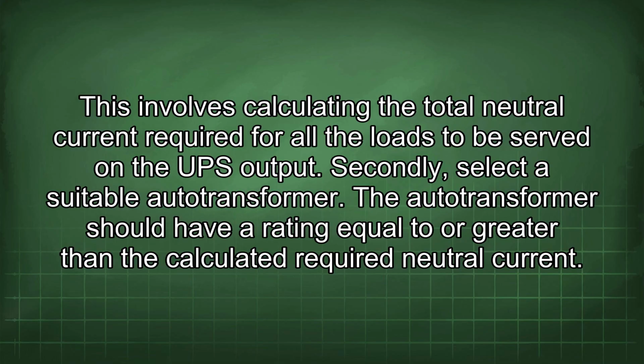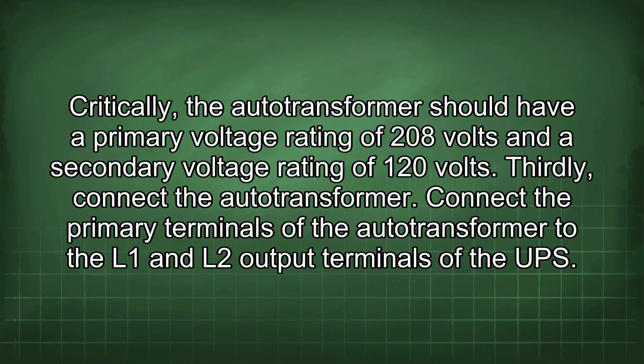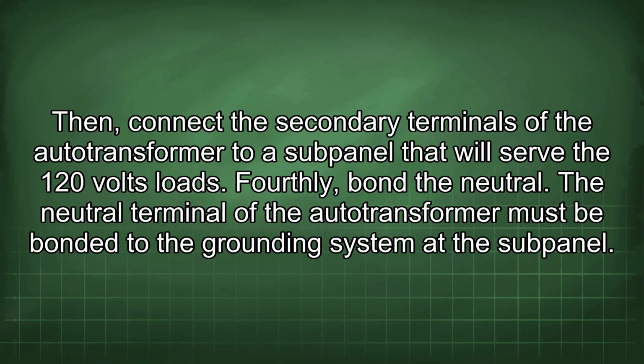Secondly, select a suitable autotransformer. The autotransformer should have a rating equal to or greater than the calculated required neutral current. Critically, the autotransformer should have a primary voltage rating of 208 volts and a secondary voltage rating of 120 volts. Thirdly, connect the autotransformer. Connect the primary terminals of the autotransformer to the L1 and L2 output terminals of the UPS. Then, connect the secondary terminals of the autotransformer to a subpanel that will serve the 120 volt loads.